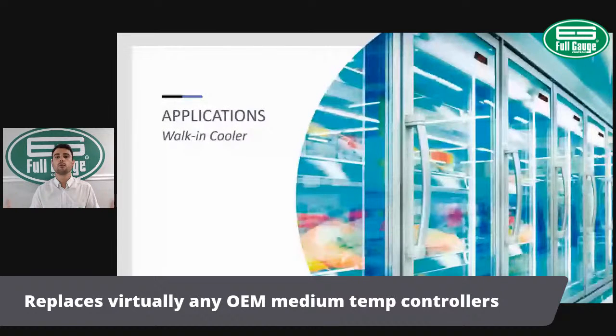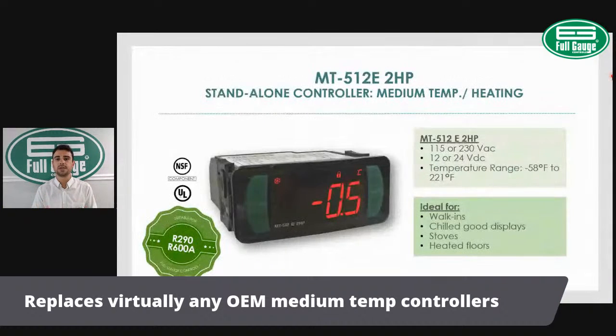So let us look at what we have. So the MT512 2HP, it's a dual voltage controller. So you can either power in 110 or 220. We also offer a version of 12-24 volts, and the temperature range with those controllers goes from minus 58 degrees Fahrenheit all the way up to 221 degrees Fahrenheit. And again, it is ideal for reach-in, upright, chest coolers, prep tables, walk-in coolers, and any type of medium temp refrigeration application that requires temperature control as well as off-cycle defrost, natural defrost.